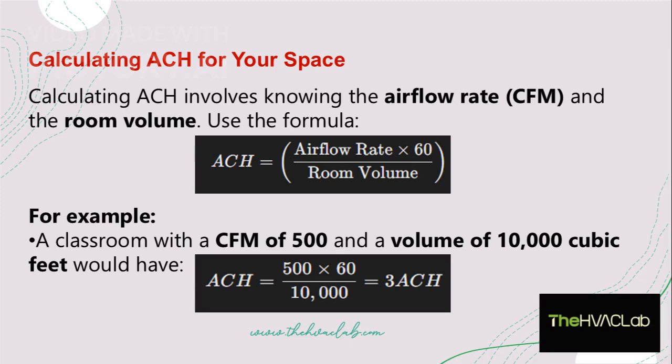To calculate ACH, you need to know the airflow rate and the room volume. For example, a classroom with a CFM of 500 and a volume of 10,000 cubic feet would have an ACH of 3.